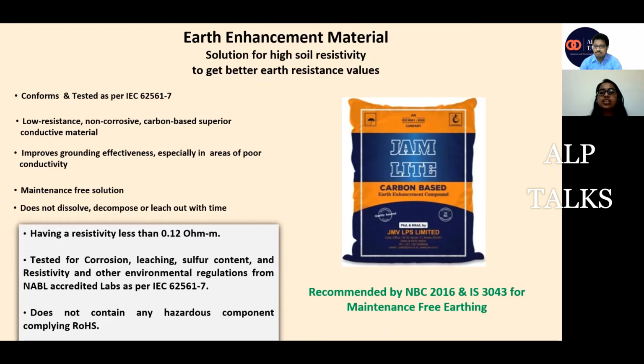The second test is the leaching test, that it will not leach out with time as salt and charcoal leaches out with time. We check the sulfur content in the compound because it is going to be installed in the soil, so it should be eco-friendly to nature. It should not pollute my soil or my ground. So this sulfur content test is done, and the other one is the resistivity test. As per standards, the resistivity should be less than 0.12 ohm meters. Only then will it serve the purpose of lowering the resistivity for higher resistivity areas. So these are the 4 tests which we generally perform as per the standard, and after that the compound or this chemical comes into play for the installations.